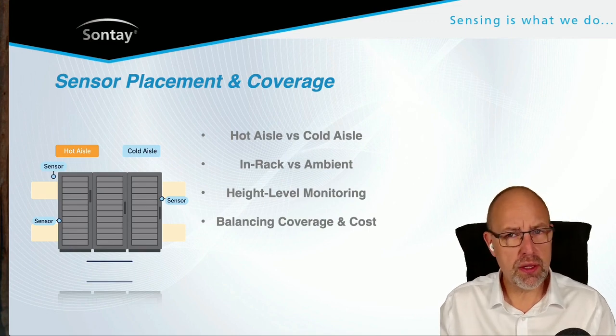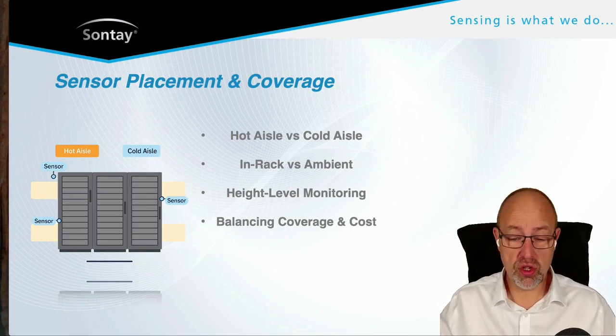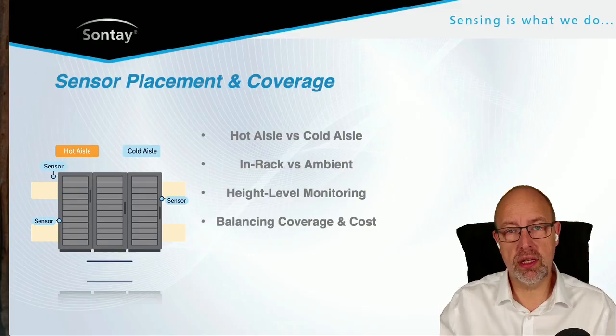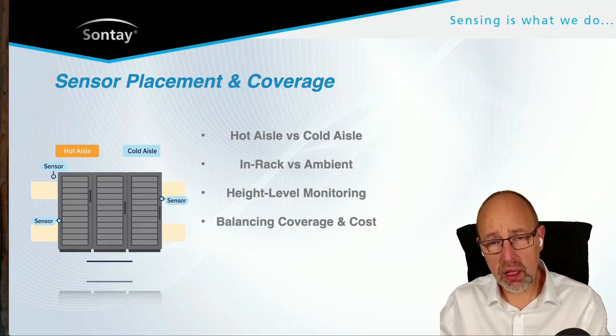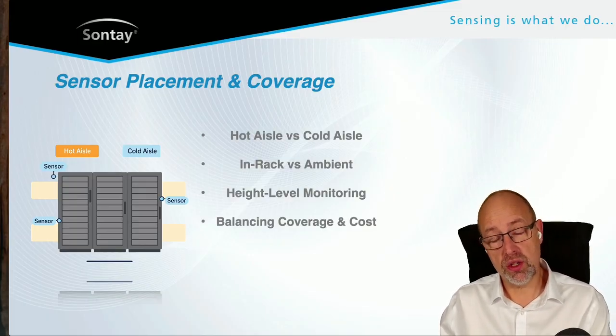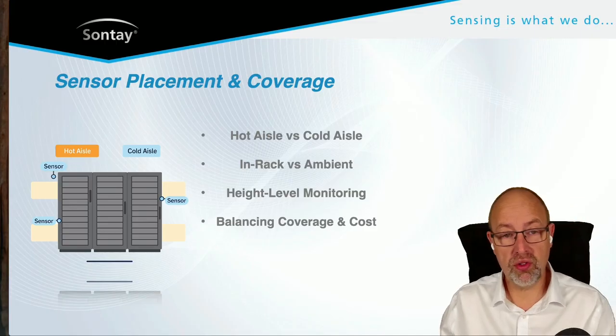In-rack versus ambient, the actual in-rack temperature can be important. It very much depends on the server technology in use, but what's going on inside the server rack itself can give you very useful insight as to whether you need to provide more or less cooling.